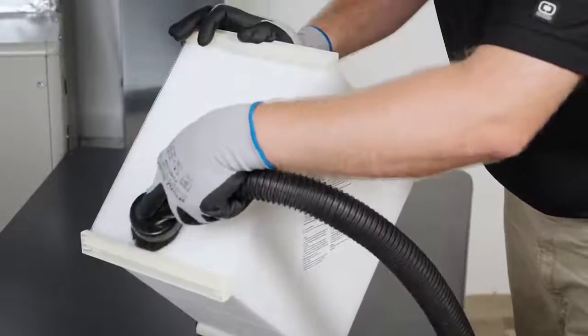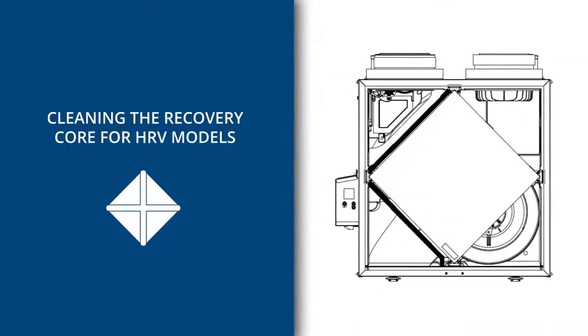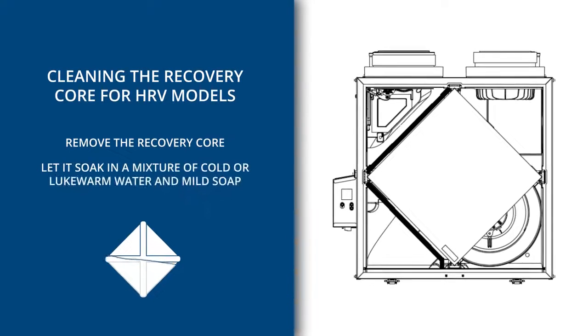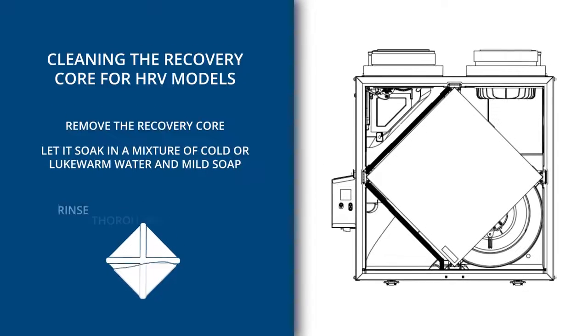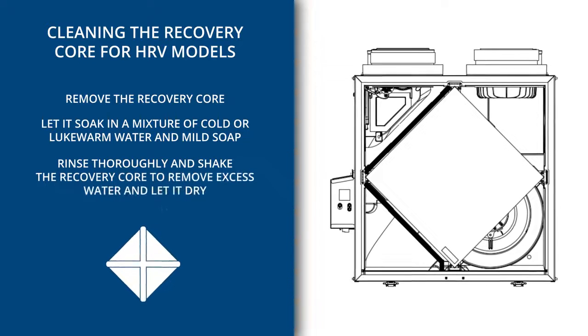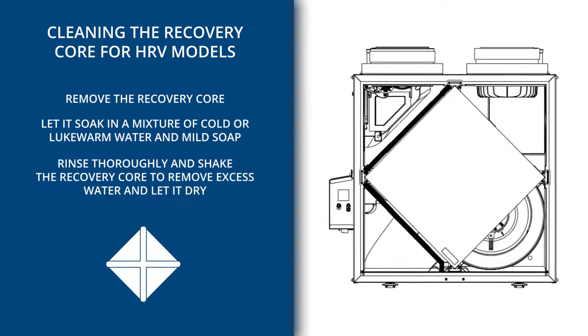Then clean the recovery core and blower assemblies. To clean the recovery core for HRV models, remove the recovery core. Remove dust using a vacuum cleaner with a soft brush attachment. Rinse thoroughly and shake the recovery core to remove excess water and let it dry.